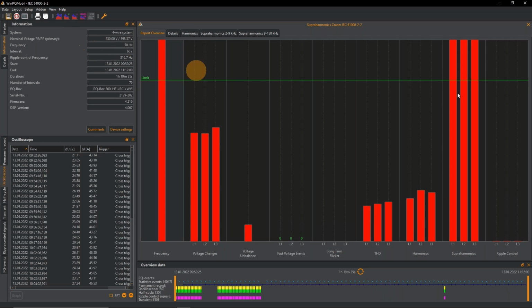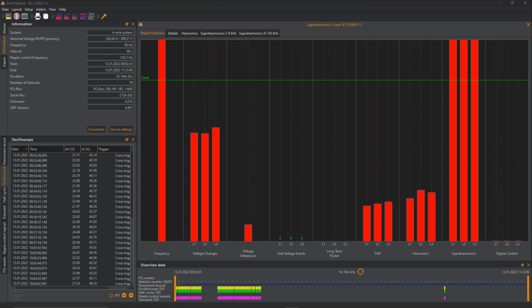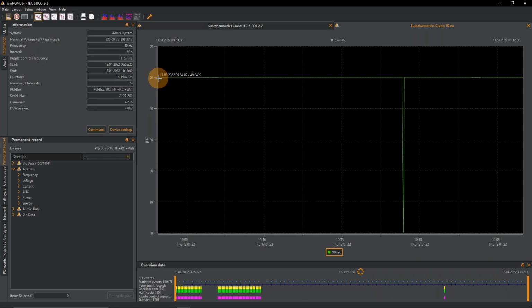This evaluates the whole measurement. So every single data point of my measurement will be evaluated against limit values. And at first glance, I see, okay, frequency, there was something wrong, and supraharmonics. I will start with the easy one because I know how the measurement was performed, and I can see everything is fine. 50 Hertz. Oh, what was there?